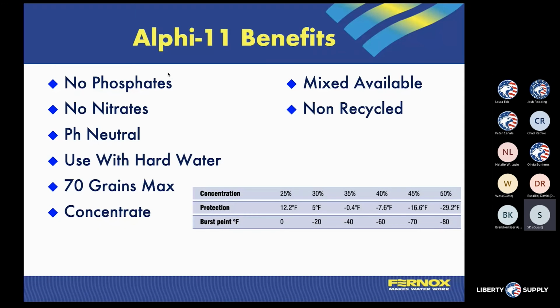So we come in a state of neutrality so that you can have your system start. And the F1 is going to automatically balance because we have the F1 built into our Alphi-11 polypropylene style glycol. The other thing is, because we're using F1, it's not a phosphate or nitrate based inhibitor. The problem with that type of inhibitor is that if it overheats or over a duration of time, it'll eventually become acidic, so you end up having to change that glycol sooner than you normally would. So we do not utilize those.